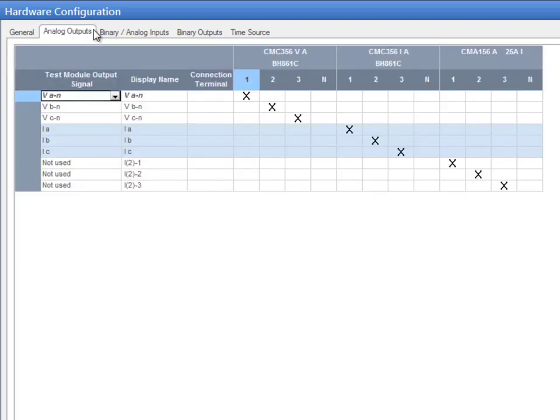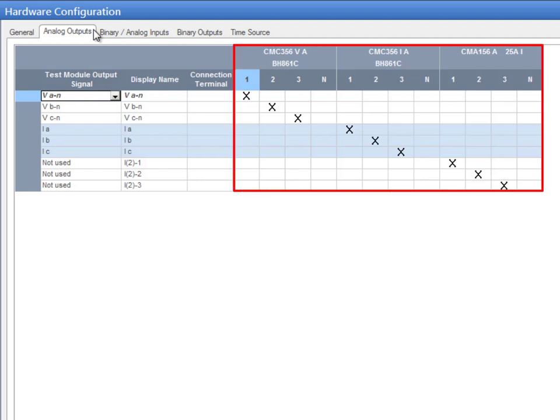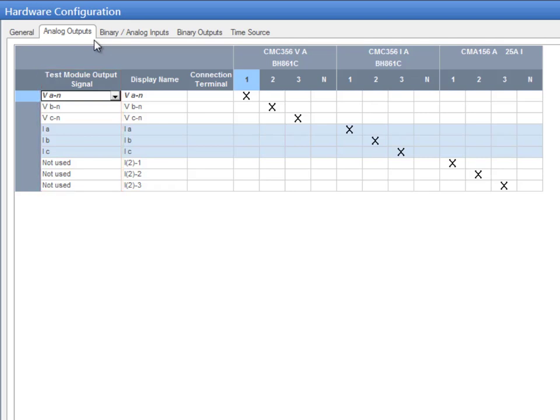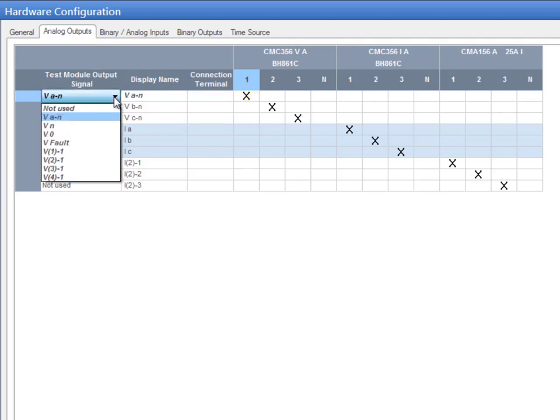The wiring matrix on the right allows you to indicate how the signals are connected to the CMC test set. The first column assigns the output signal of the test module to the CMC test set output specified in the same line. This means that the voltage in Phase A is assigned to CMC output 1. The drop-down menu only displays the signals that a specific test module might need to conduct a test.